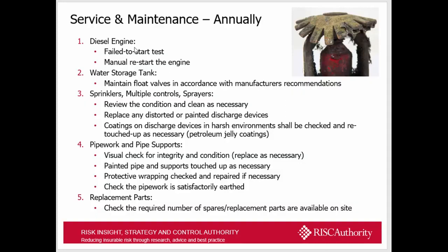Any coatings on sprinklers in harsh environments, you can get jelly coatings. They need to be touched up as necessary. You should also be checking pipework supports. You should be checking visually for integrity and condition and replace where necessary, and any pipe that's been painted needs to be touched up. Any protective wrapping should be checked and repaired, and check that the pipework is satisfactorily earthed.